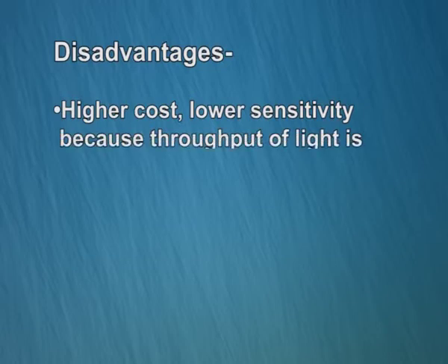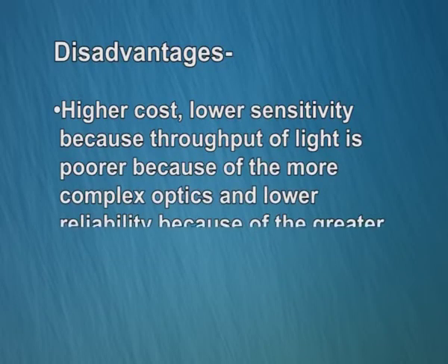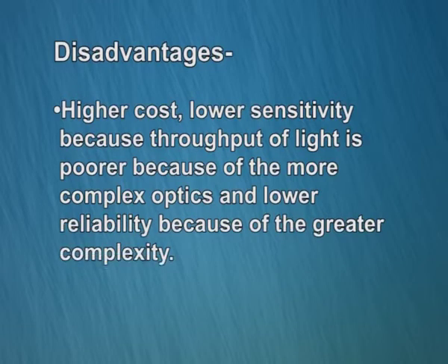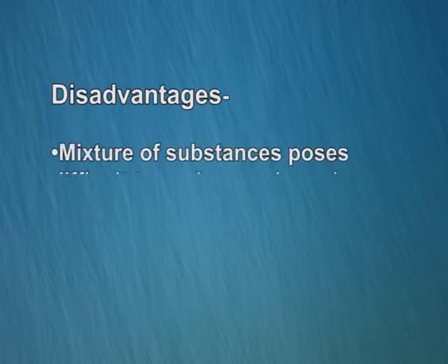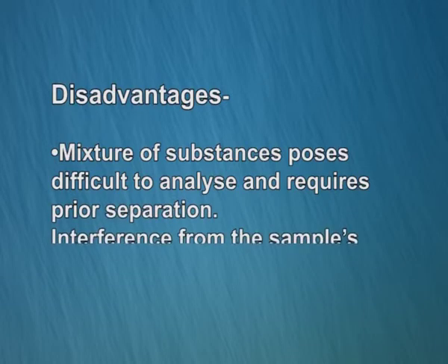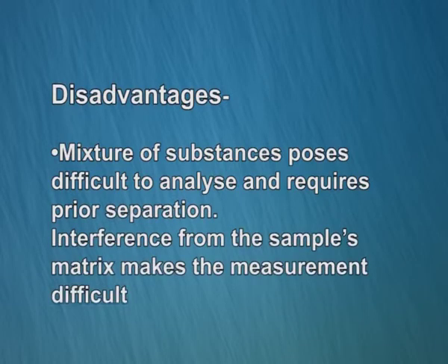Disadvantages: higher cost, lower sensitivity because throughput of light is poorer because of the more complex optics, and lower reliability because of the greater complexity. Samples should be in solution. Mixture of substances is difficult to analyze and requires prior separation. Interference from the sample's matrix makes the measurement difficult.